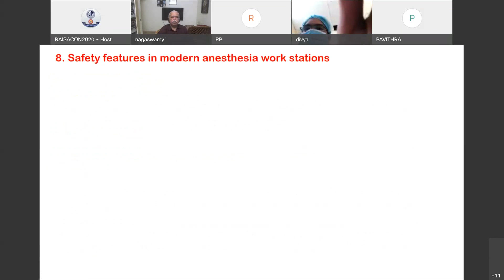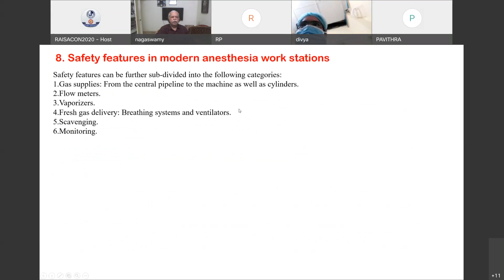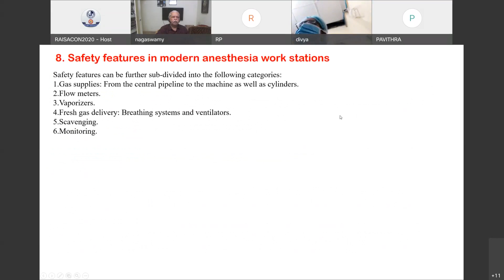Now coming to the last question, safety features in a modern anesthesia machine. You can subdivide them into safety features in gas supply, flow meters, vaporizers, fresh gas delivery, that is the breathing system, ventilators, scavenging, and monitoring. These are the 6 headings under which you can classify the safety features. Then you can again classify the gas supply into the high pressure system, where gas cylinders are color coded to prevent the wrong gas being used, with international safety standards, and there is a pin index system. These are the basic 2 things that you have to remember about the gas cylinders.